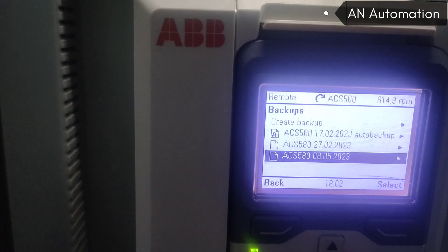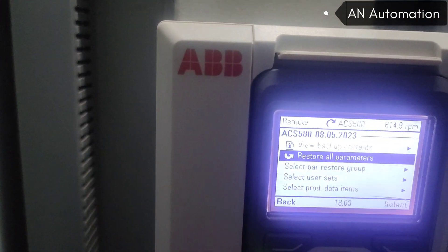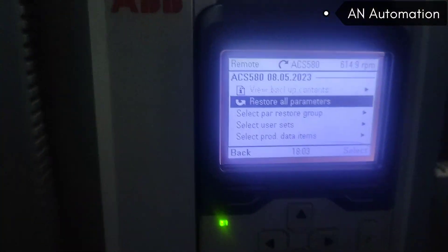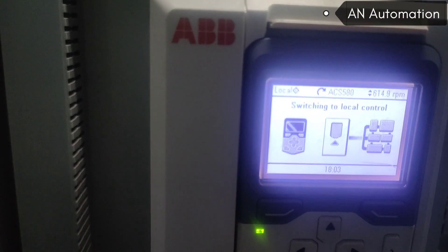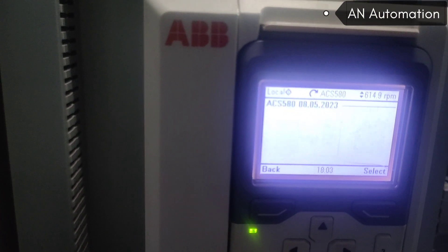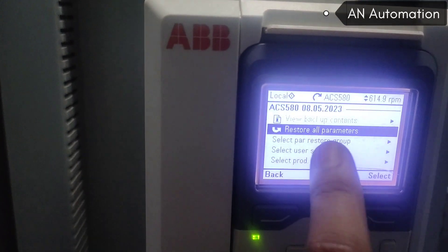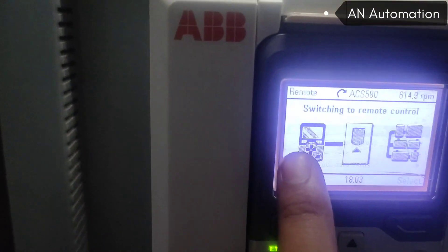Now you can see that when you open and select 'Restore All Parameters', the option is not selectable. But when you switch the drive from remote to local — if you select local — then you can select 'Restore All Parameters'. When it is in remote mode, you cannot restore all parameters.